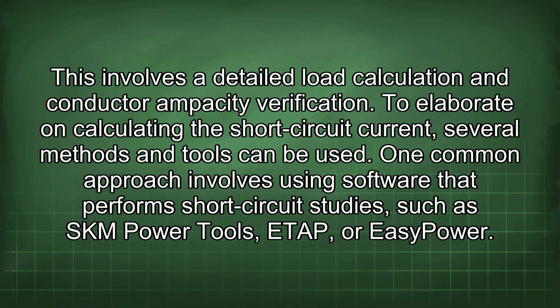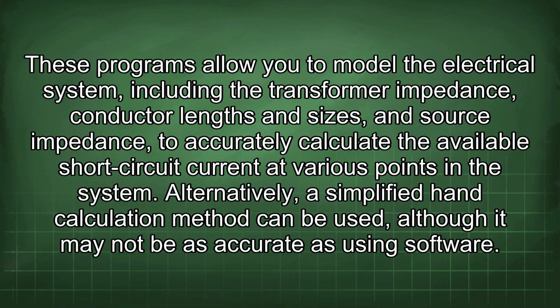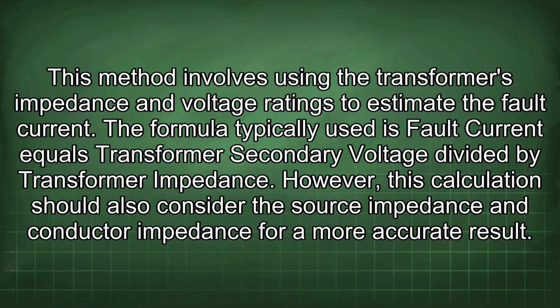To elaborate on calculating the short-circuit current, several methods and tools can be used. One common approach involves using software that performs short-circuit studies, such as SKM Power Tools, ETAP, or EasyPower. These programs allow you to model the electrical system, including the transformer impedance, conductor lengths and sizes, and source impedance, to accurately calculate the available short-circuit current at various points in the system. Alternatively, a simplified hand calculation method can be used, although it may not be as accurate as using software. This method involves using the transformer's impedance and voltage ratings to estimate the fault current. The formula typically used is fault current equals transformer secondary voltage divided by transformer impedance. However, this calculation should also consider the source impedance and conductor impedance for a more accurate result.